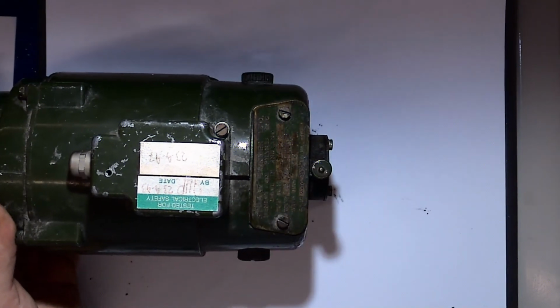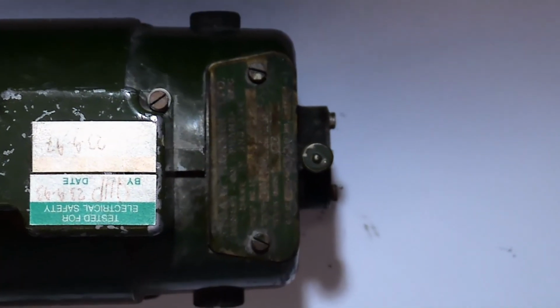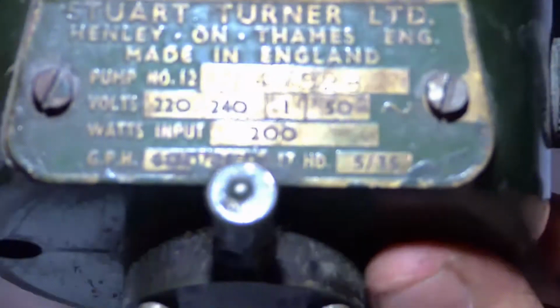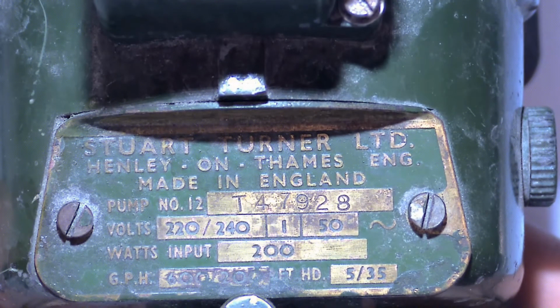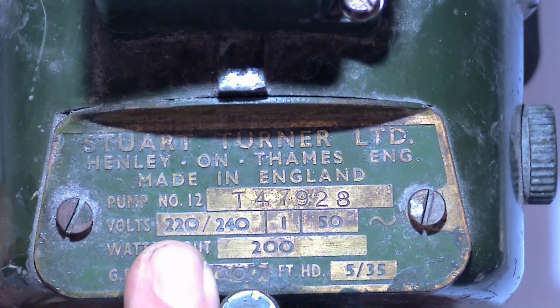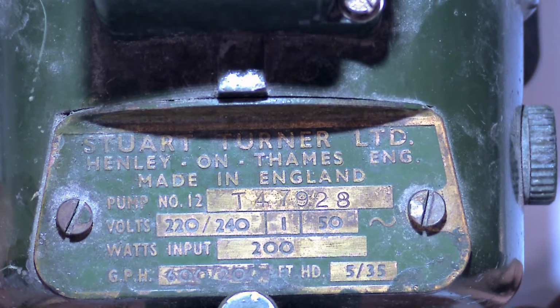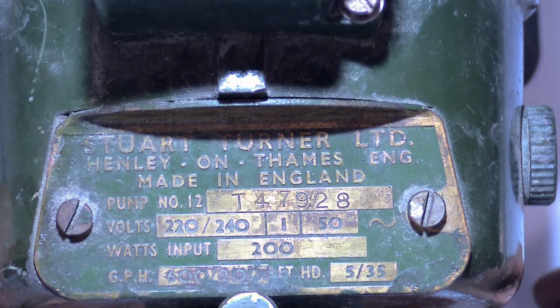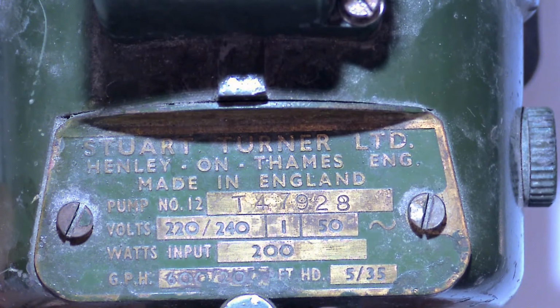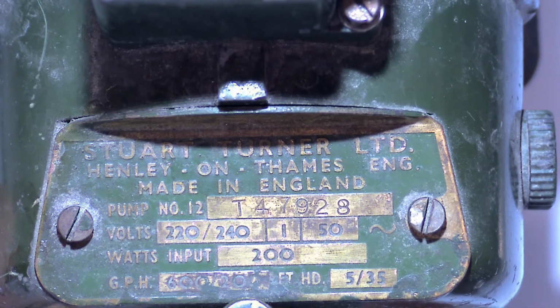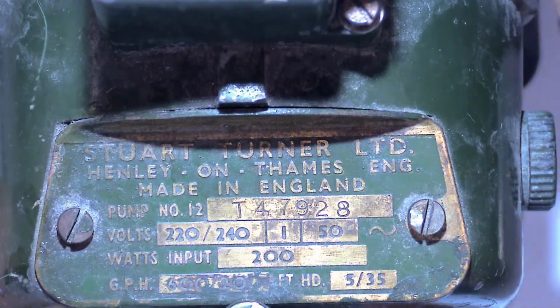So let me zoom in a little bit and you'll see. Might see better if I put it in the correct orientation. There we go. It's terrible focus as well, isn't it? There you go. You've got your makers label, pump number, your input voltage 230. That's your standard household single phase supply. And at the bottom here you've got your pumping rate. It's pretty hard to read because it's all worn and old. So that's how you specify your pumps. Okay, so again, just to repeat, it's an impeller, centrifugal pump.